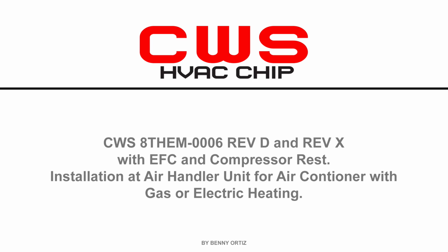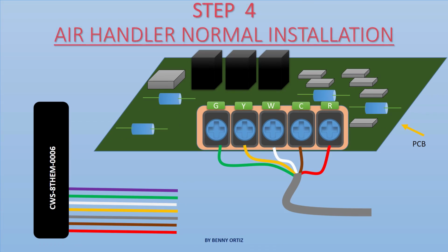Following is the procedure for CWS 8THEM-0006 Rev D and Rev X with EFC and compressor rest. Installation at the air handler unit for air conditioner with gas or electric heating. After taking a photo of the existing wiring, loosen the screw of the R or RC or RH terminal where the usual red wire is connected as shown in the video. In rooftop unit, there is only one R terminal.